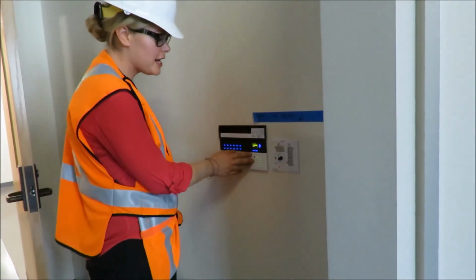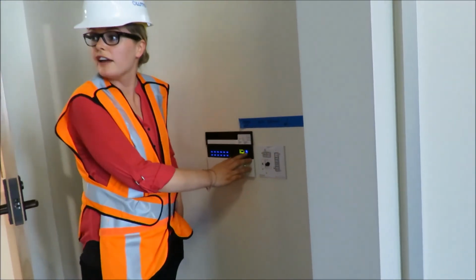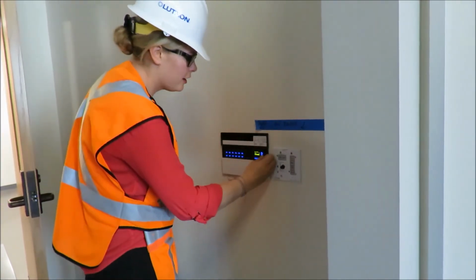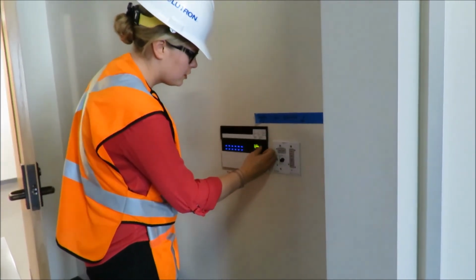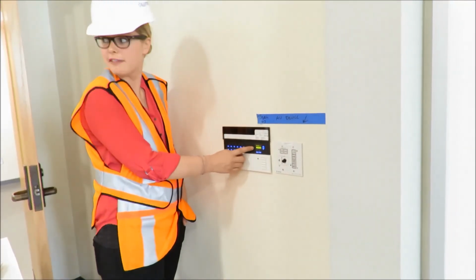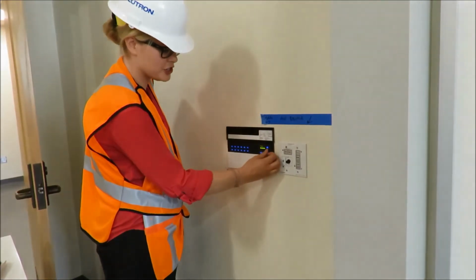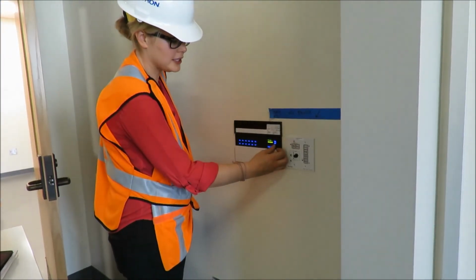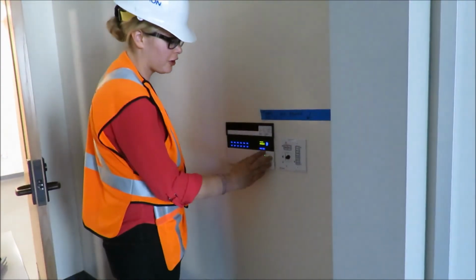Okay, and for occupancy, like I was saying, I set up scene 5 for your occupancy so that the main lights turn on, but the rest of the lights do not. You would go to actions. Occupied is scene 5, but you could change it to scene 4 or 2. Unoccupied is scene off, which is after 15 minutes of inactivity. It'll turn off.